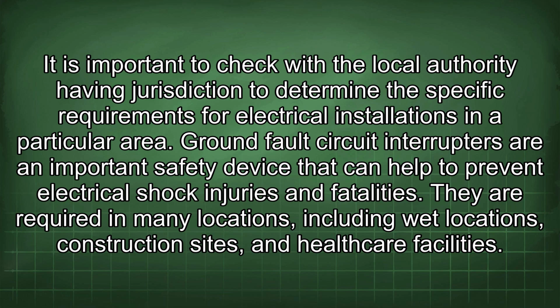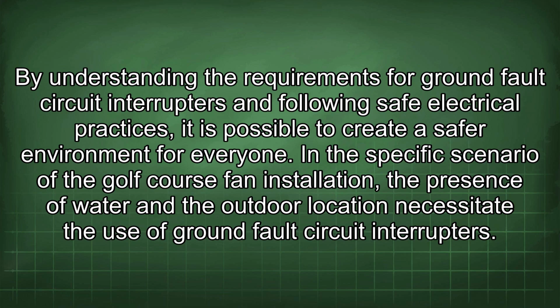It is important to check with the local authority having jurisdiction to determine the specific requirements for electrical installations in a particular area. Ground fault circuit interrupters are an important safety device that can help to prevent electrical shock injuries and fatalities. They are required in many locations, including wet locations, construction sites, and healthcare facilities. By understanding the requirements for ground fault circuit interrupters and following safe electrical practices, it is possible to create a safer environment for everyone. In this specific scenario of the golf course fan installation, the presence of water in the outdoor location necessitates the use of ground fault circuit interrupters.